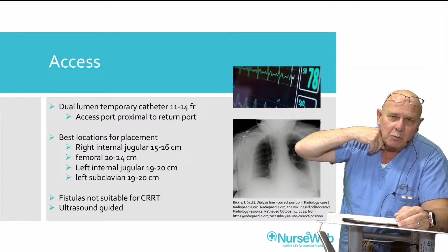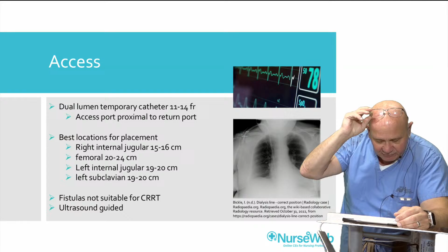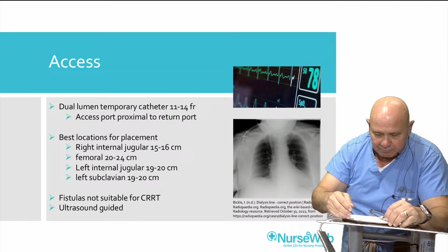You will tend to have more recirculation and more catheter failure in the other locations. The nice thing about the right IJ is it's just a straight line, right? It just goes straight up and down. It doesn't have any curves. And it's extremely important to remember that temporary dialysis catheters are intended to be hubbed, meaning you don't want part of the catheter sticking out. They're very susceptible to damage. You want that catheter buried in the patient with the harder part of the plastic right up against it. Fistulas are absolutely not suitable for CRRT, and of course using ultrasound guidance really does help in terms of inserting these things.